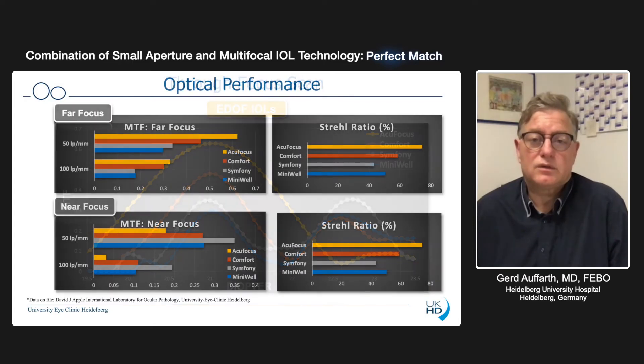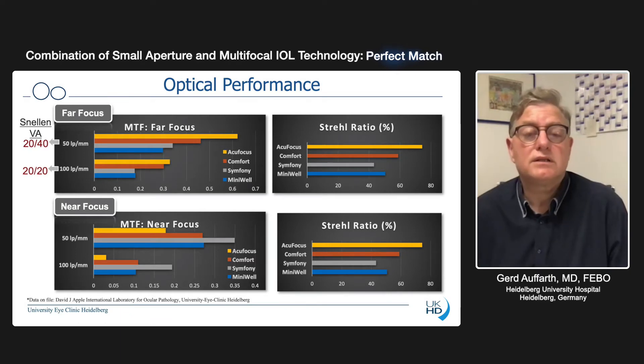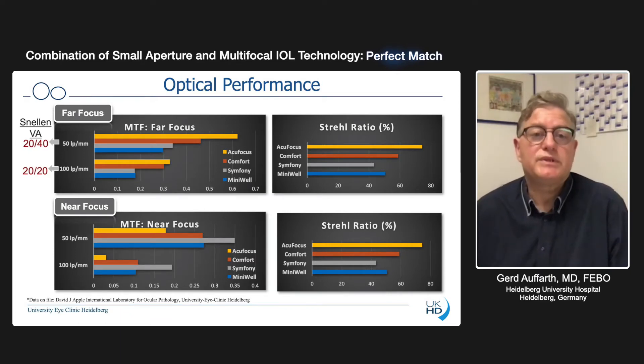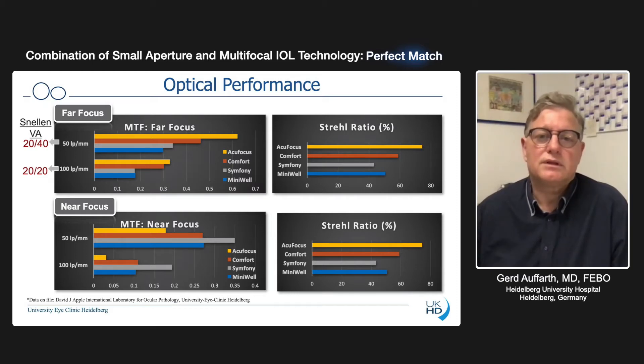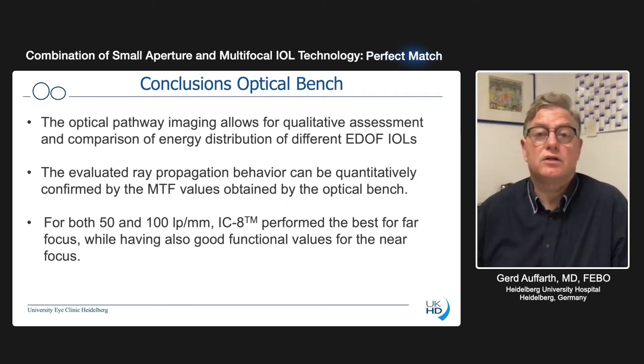It's very high quality. Looking at the MTF numbers for 50 or 100 LP per millimeter — which represents visual acuity of 20/40 or 20/20 — for distance, the AcuFocus is the best. The Strehl ratio for near AcuFocus is also best, because this is more or less the area under the curve. For normal near focus, the MTF of others is similar or a little bit better, but in general the MTF and Strehl ratio of the IC8 lens is the best compared to all the others. We can summarize that here in the conclusion slide.